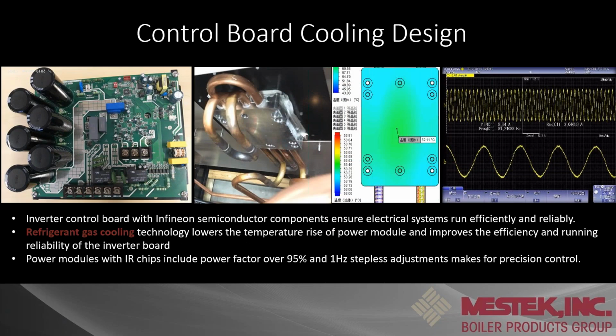So, control board cooling. I think a lot of you are used to VFD motors and how temperature can really affect how they work. Let's just say we're in a boiler room, I've got a VFD there. If it overheated, it would stop working. That's why they have cooling fans on there. Well, with this, we added a small heat exchanger into that DC driven board, and that is keeping the temperature down. So we're making sure if it's super hot out, we're still keeping it nice and cool on that control so it never overheats and we don't have any issues. I find it to be a really cool design that was added, just to protect the board and make sure it never overheats.